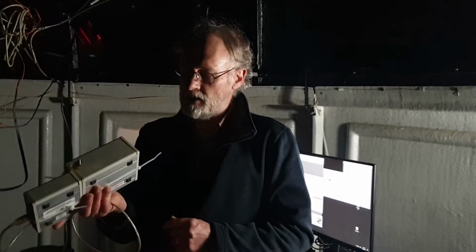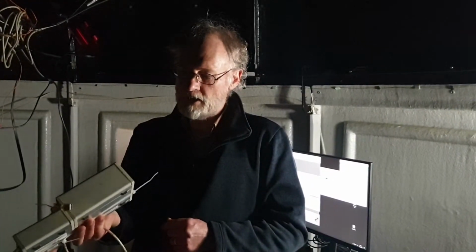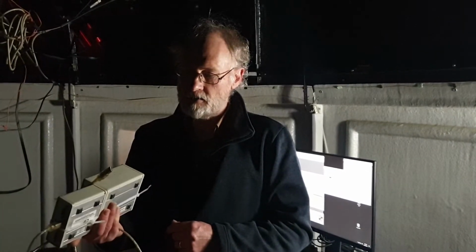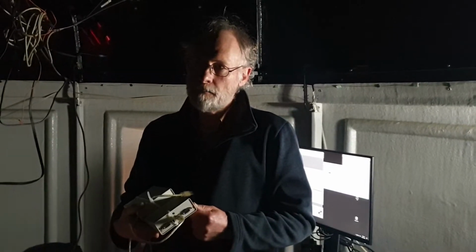The thing about that spectrometer is, unlike this one here, where we're not really sure about the wavelength range, and the calibration is tricky, a bit messy and temperature sensitive, the Fourier transform spectrometer has a resolution that's many, many times higher. Its frequency is really well calibrated because it uses a reference to a helium-neon laser. So it has a range of advantages, and we just happen to have a high resolution Fourier transform lab right beneath our feet. Yeah, just over there.